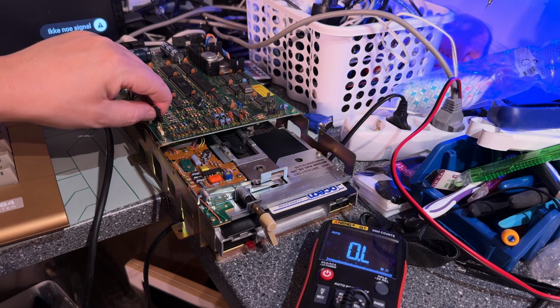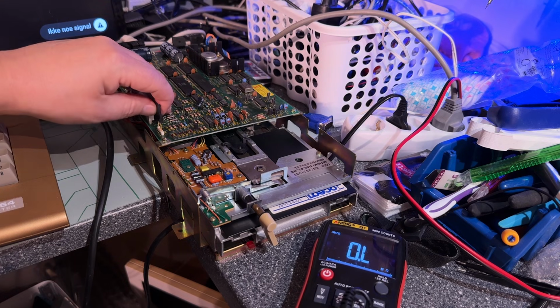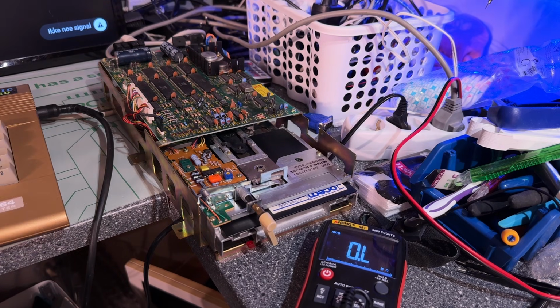Yeah, so I don't think there's anything wrong with that. Because if it's an open or very high resistance connection, then it would indicate that the drive head is dead, and apparently it's not. It should be under 100 ohms, I think.